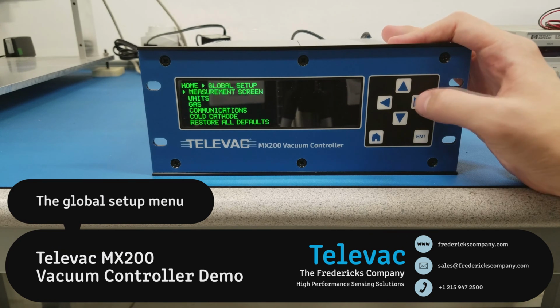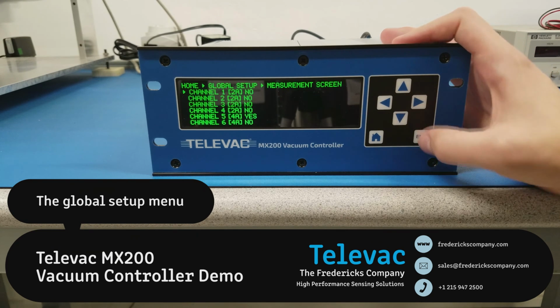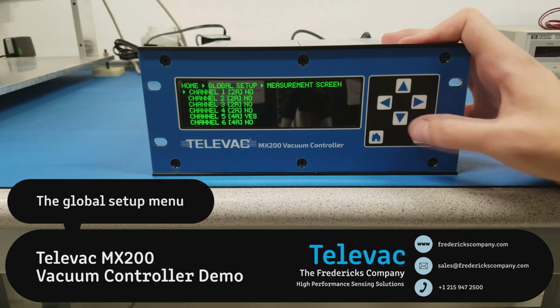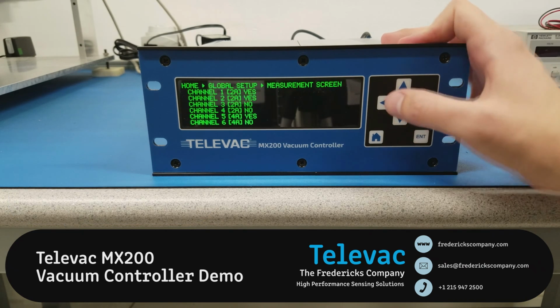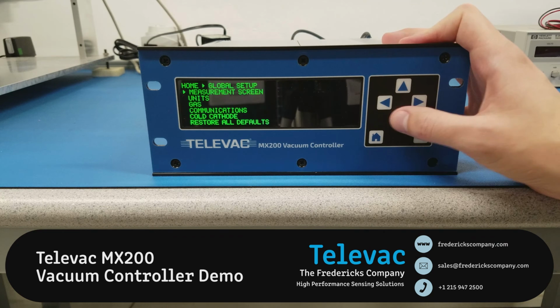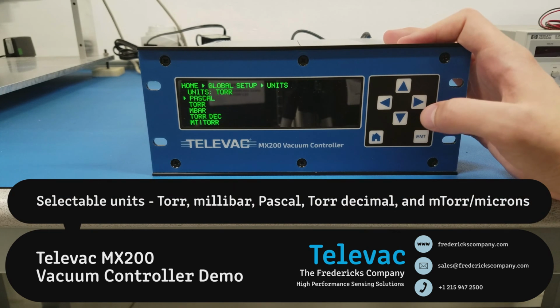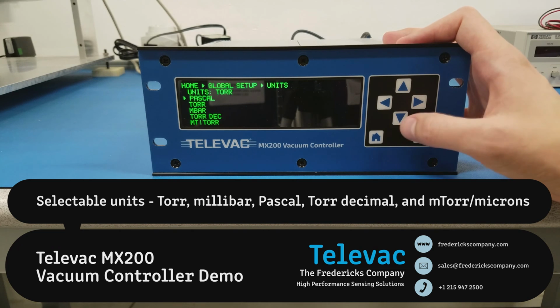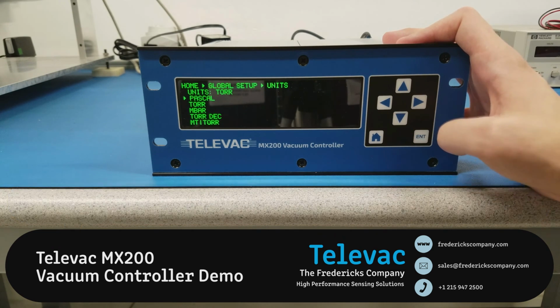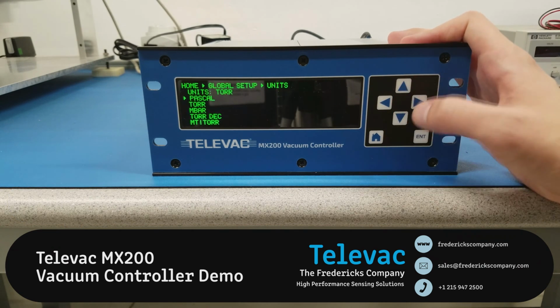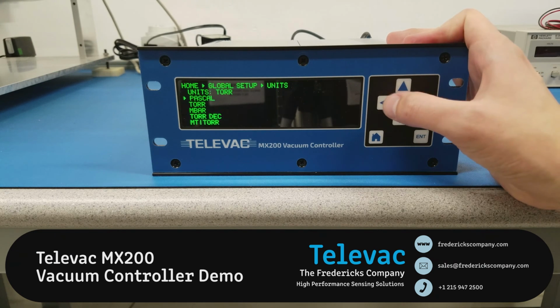So we were in here before. You can adjust what channels are displaying by hitting enter on any of the channels to toggle it between on and off. We can here also adjust the units. So the options are Pascal, torr, millibar, torr decimal, and millitorr. So these are explained in more detail in the manual if you want to review them.